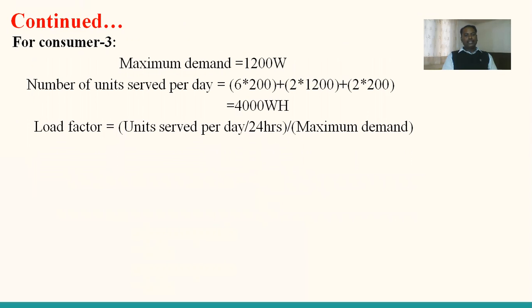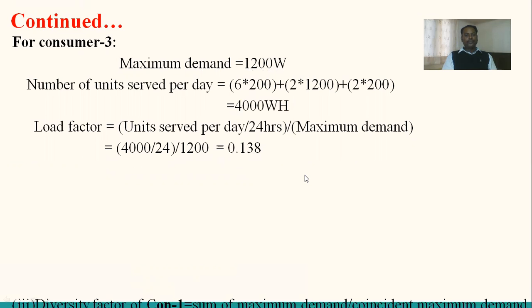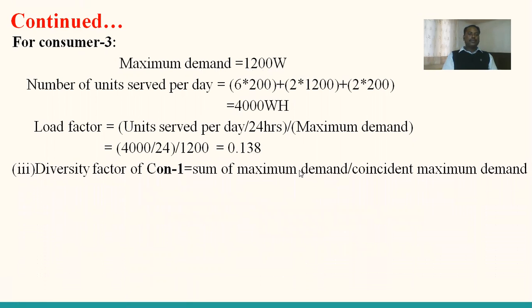So here also the same thing, load factor. You can calculate the load factor. The maximum demand is 1200 watts. So the resulting value is 0.138. So therefore, the maximum demand and load factor of the consumers are calculated for the 3 consumers, and we need to go for the diversity factor of the consumers.